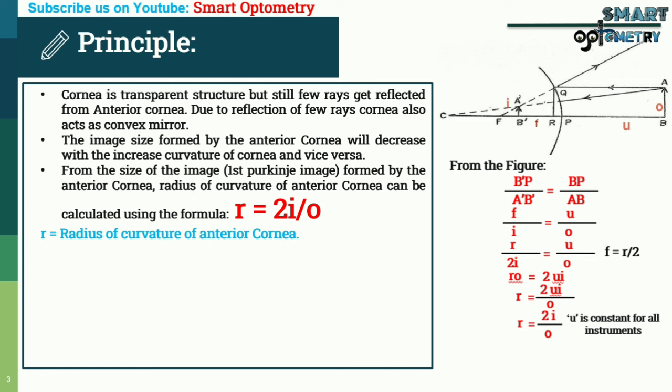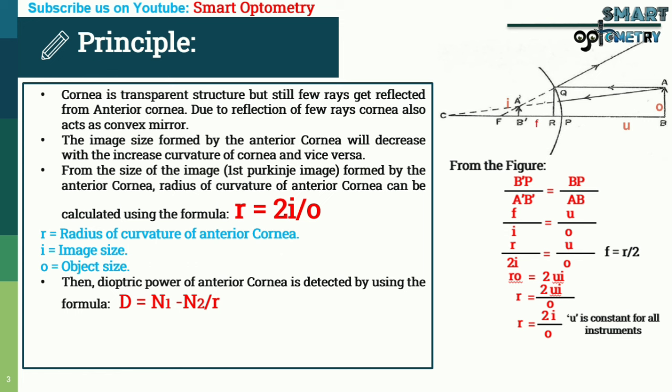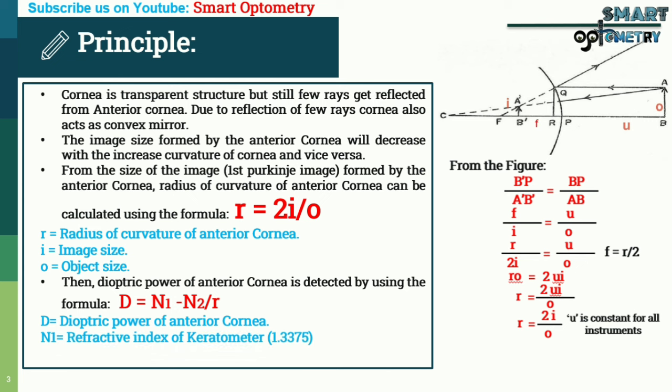In the formula R = 2i / O: R is the radius of curvature of anterior cornea, I is the image size, and O is the object size. The dioptric power of anterior cornea is detected using D = (N1 - N2) / R, where D is the dioptric power of anterior cornea, N1 is the refractive index of the keratometer (1.3375), and N2 is the refractive index of air (1).